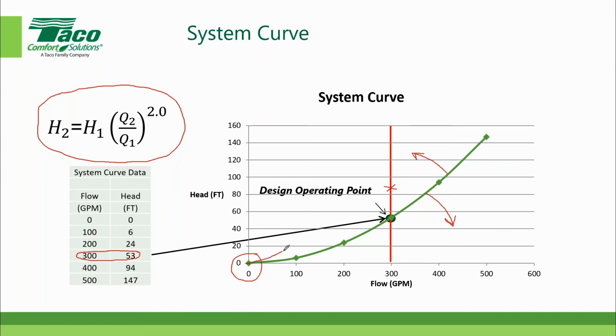Then I would draw a new system curve that would come up here and bend upwards to the left. You get the general idea. Now, if the pressure differential was not 53 feet, maybe it was less than that, maybe it was 30 feet down here, then I'd have a system curve that bends downwards to the right. Kind of get the idea. So any questions about the system curve, how we generate it, and the effect of the pressure in the system, where the curve bends upwards to the left if we have more pressure, or downwards to the right if we have less pressure? No questions pertaining to the system curve.